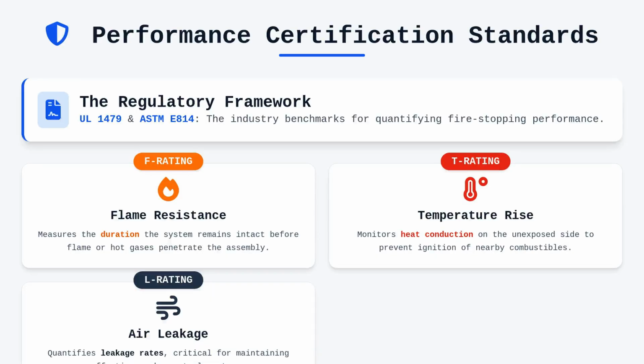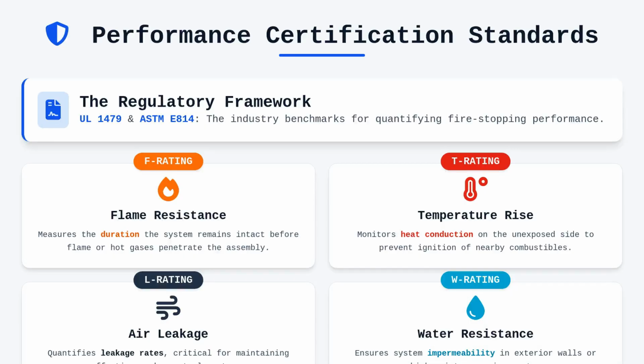We might also see L ratings, which quantify air leakage rates, a vital statistic when you are dealing with smoke control systems. Finally, the W rating ensures that the system is resistant to water, which is often overlooked in exterior wall applications or areas prone to high moisture levels.